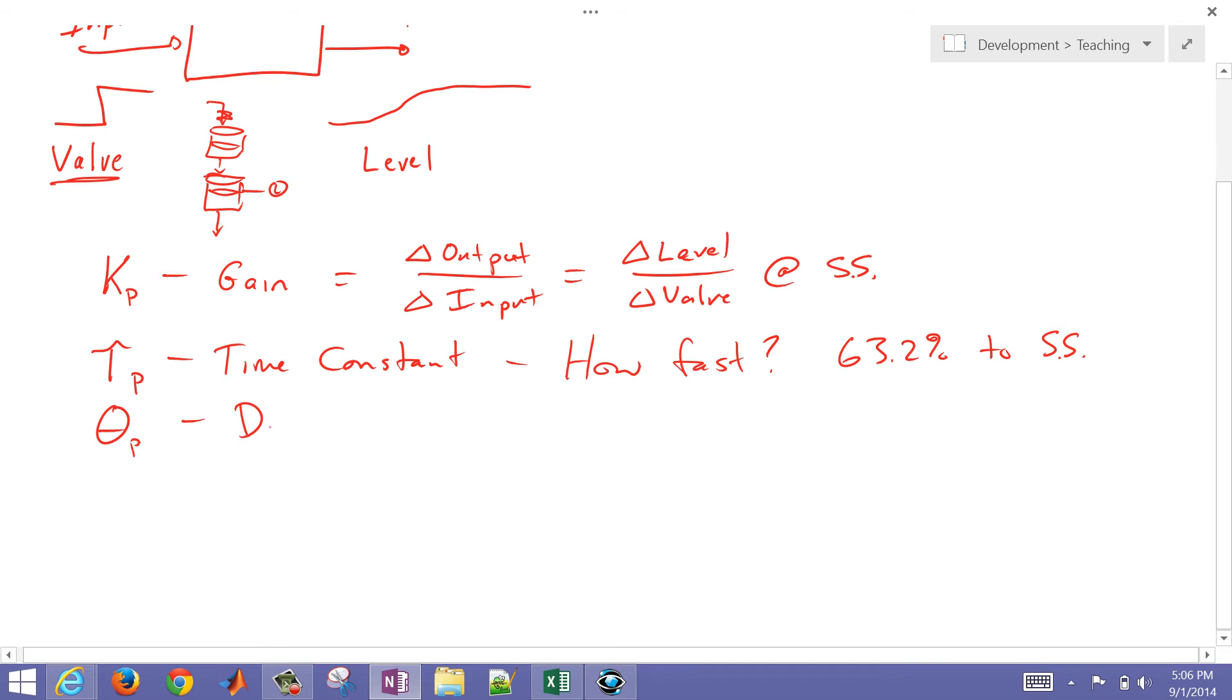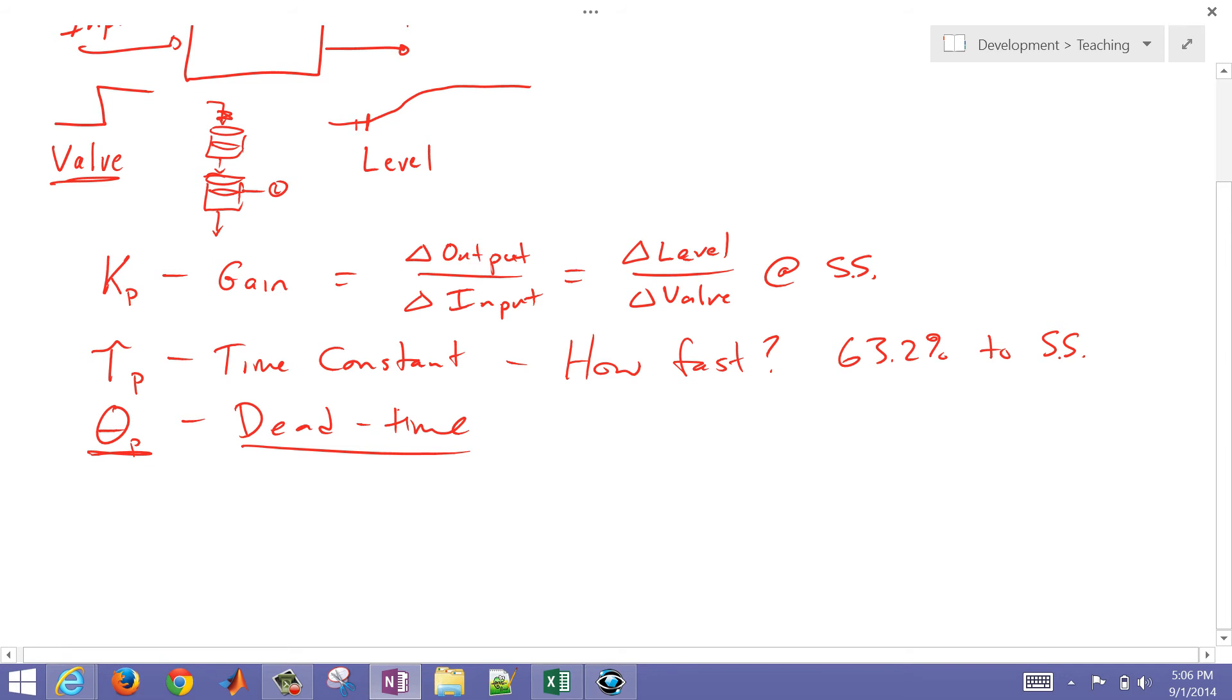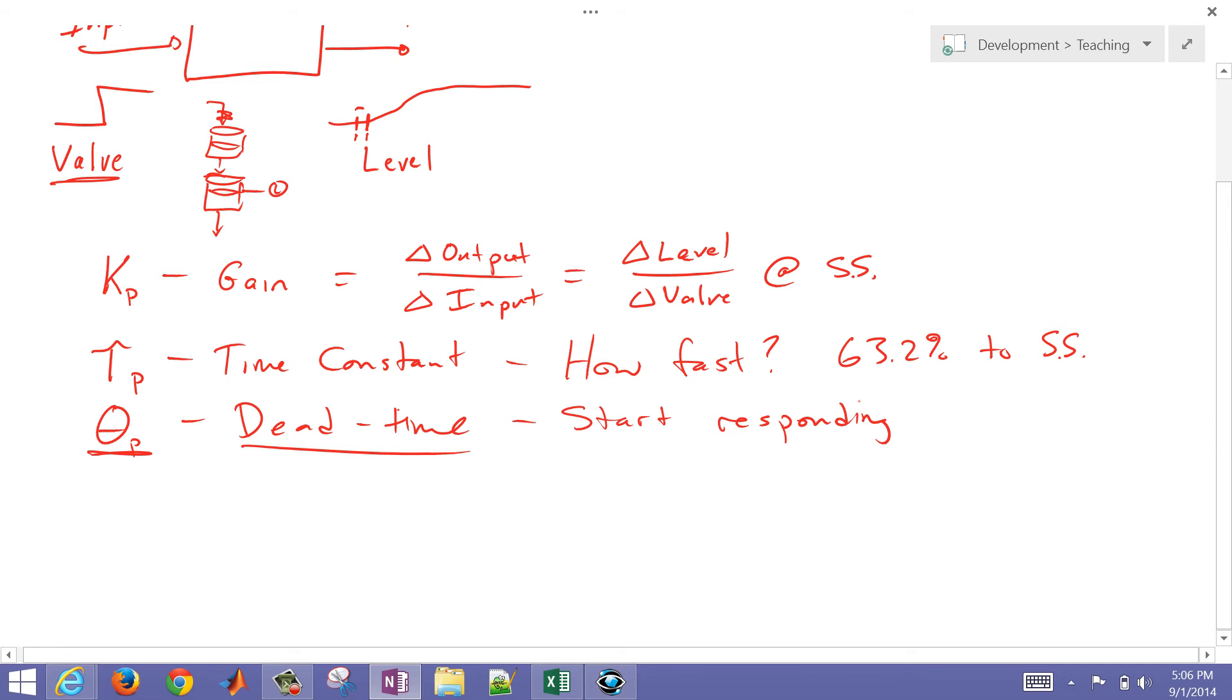And then the final thing that we're going to have is an apparent dead time. We're going to use a first order system, and this is a dead time that, when you move the valve, let's say you started moving the valve here, that's about how long it took for it to start responding. So that is the dead time, the amount of time to start responding to the change. With just these three, we can model many, many dynamic systems.